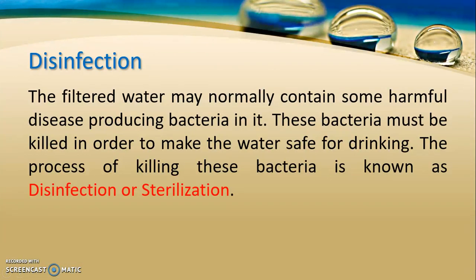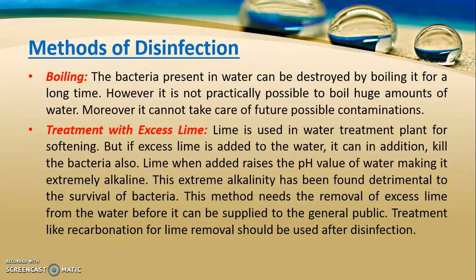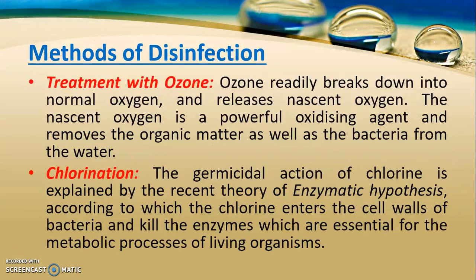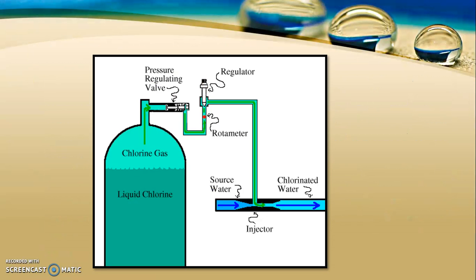After filtration comes the disinfection process. In a water treatment plant, much of the bacteria is not removed in a rapid sand filter due to its limited efficiency. Disinfection is the process of killing bacteria present in the water. There are different methods of disinfection: boiling (used in households especially during rainy seasons), treating with lime, treating with ozone, and chlorination. Boiling is not practically feasible for large quantities in a water treatment plant, so chlorination — using chlorine gas — is the most common method used.